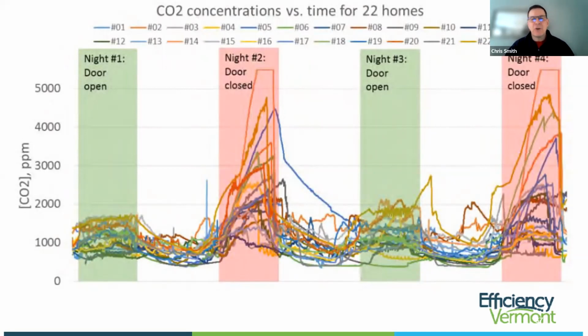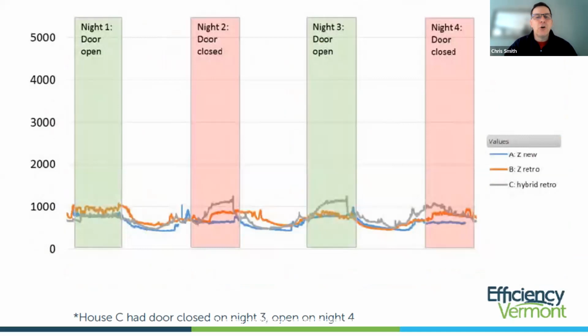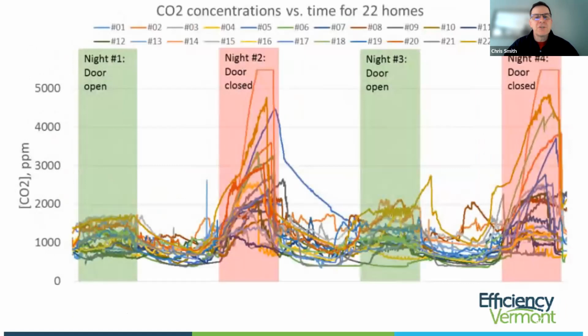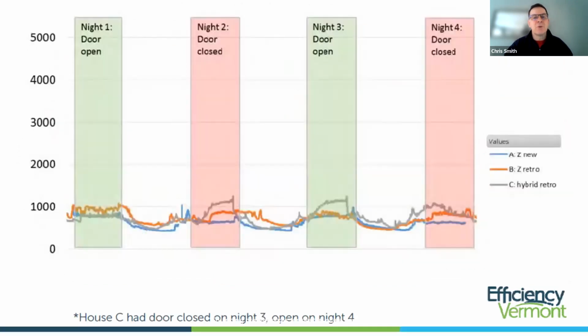Now, none of that says very much about the method of air distribution until we separate out the homes. Here we have 3 homes where the air distribution method targeted the bedrooms so that fresh air supply was being delivered directly to the bedrooms. So if you compare 19 other homes where it wasn't, we can see very high CO2 levels in those bedrooms versus the homes where fresh air was delivered directly to the bedrooms.